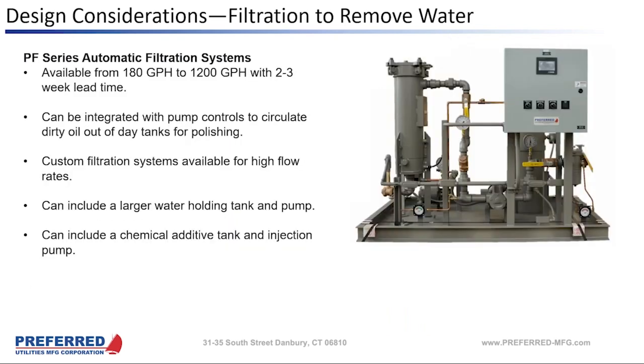Okay, so the polishers are available from 180 gallons per hour to 1,200 gallons per hour. We have all the components in stock to make one, so the lead time is fairly short, 2 to 3 weeks. Most of them get standard programs. I never use the smallest two sizes. I think the PF503 is 600 gallons per hour, so it seems like the bigger fuel systems I see out west, we're always using 600, 900, or 1,200 gallons per hour. And we may develop a bigger polisher too, to keep up with the Joneses. We've done larger polishers with larger pumps, but they become skid-mounted units like what you see in this picture.